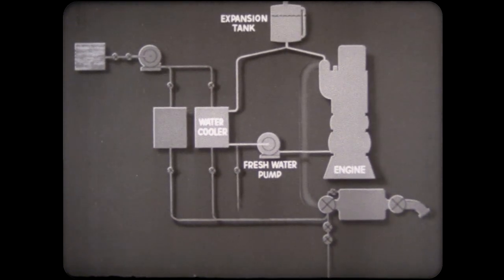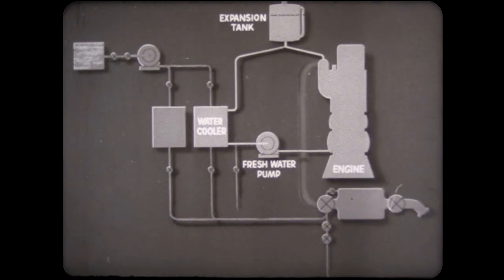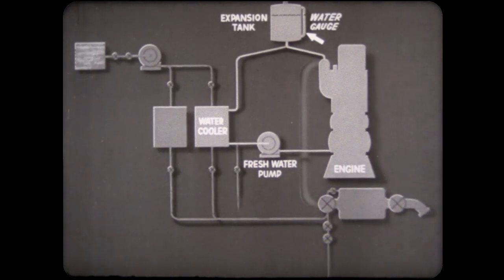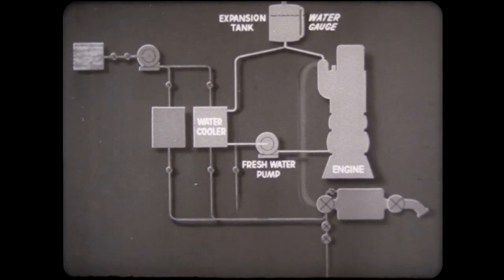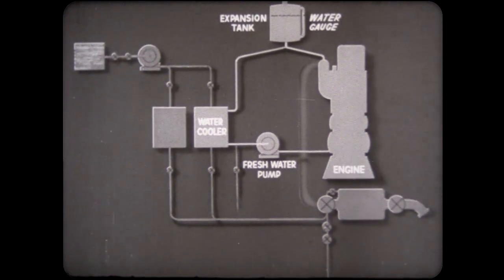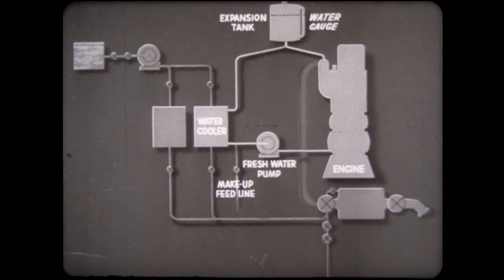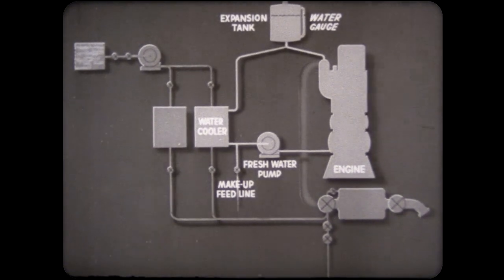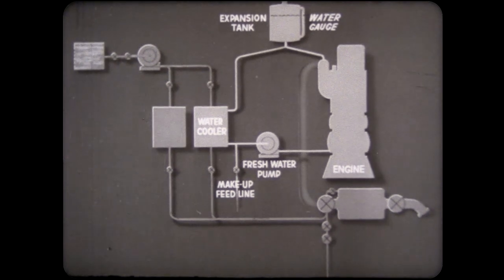An expansion tank is located at the highest point on this line. A sight gauge mounted on the tank indicates the amount of water in the system. The make-up feed line for adding fresh water is located at the suction side of the pump. Pressure gauges and thermometers are placed at various points in the system.